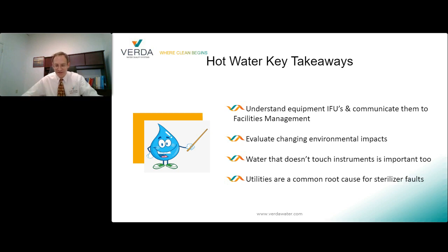And here's a fun fact. Utilities are often the common root cause for medical equipment issues. So water chemistry, water pressure, water temperature, they are all important. Don't forget about your drains. If you have underside drains that back up, that can cause sterilizers and washers to fault. And we're talking about water today, right? But just how clean is your power, right? And if your sterilizers use compressed air, how consistent is your pressure and your dew point of the compressed air, right? All these factors need to be considered.